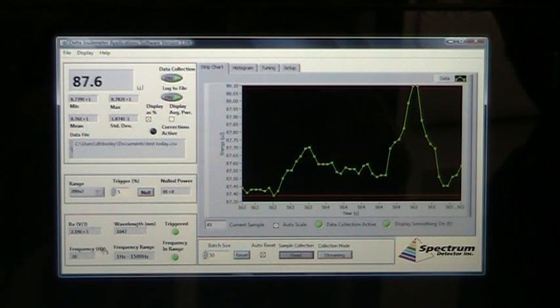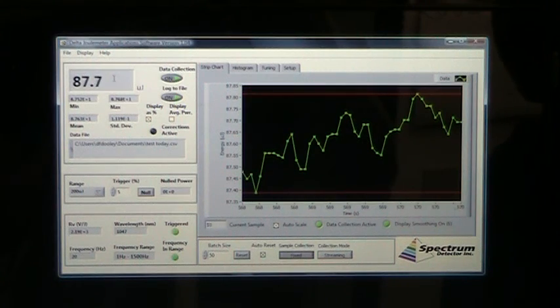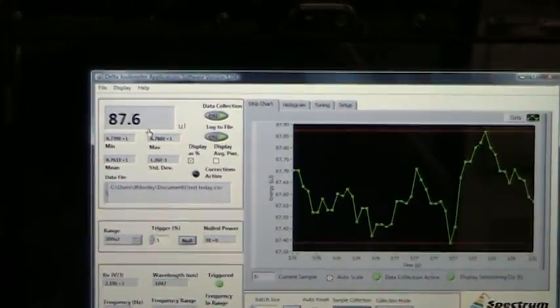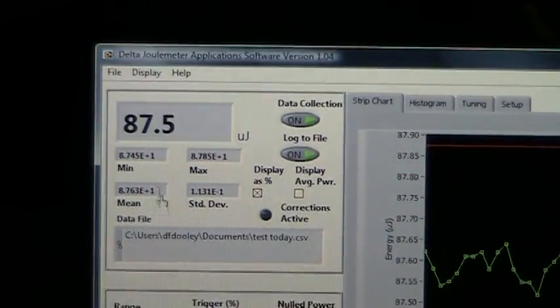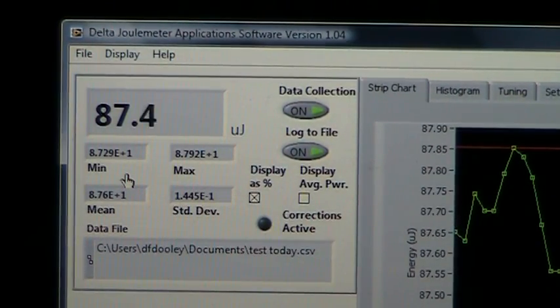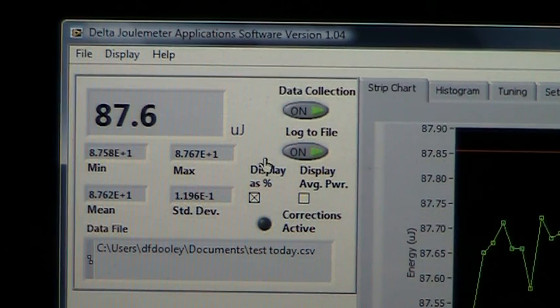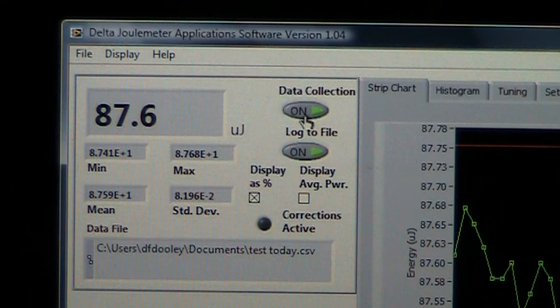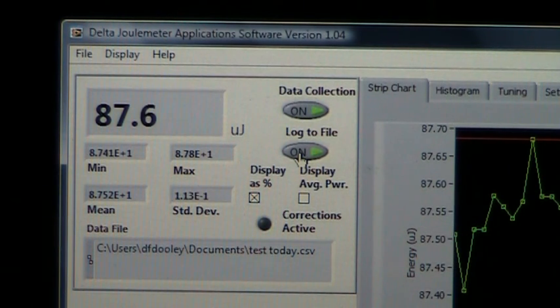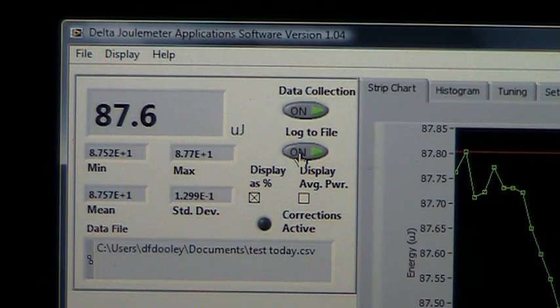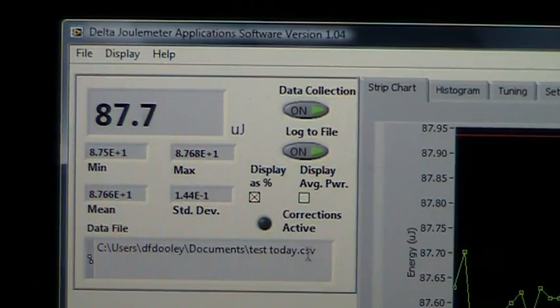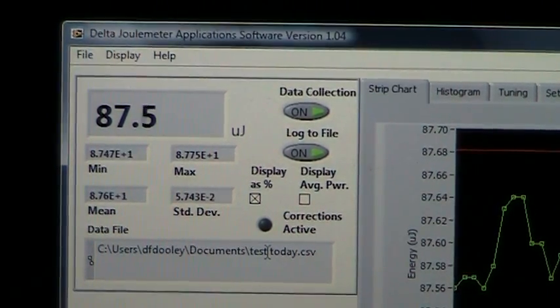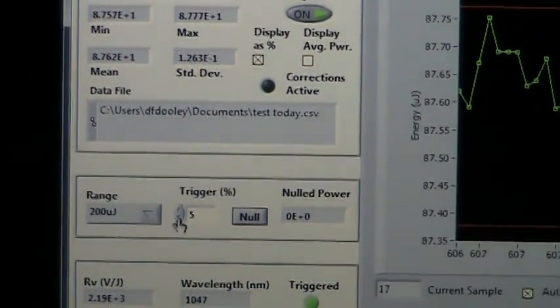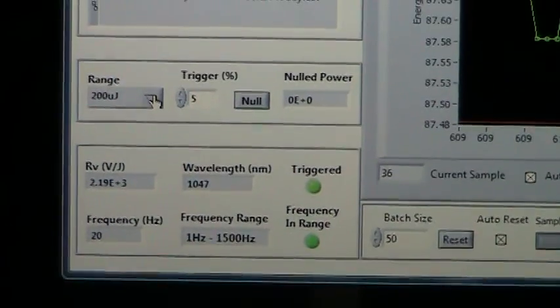This is revision level AM. This is the control panel, which is always visible to the user. In the upper left hand corner is a large window where we display pulse energy in real time. We're reading about 87 microjoules right now. Just below that are 4 windows where we display the calculated statistical data set: min, max, mean, standard deviation. Up in this right hand corner is the data collection button. This is how you turn data collection on and off. Just below it is a log to file button to log data to a file on your computer, and this window actually shows the file we have open to which we log the data. Now moving below this area we get to a couple of the controls. This is a range switch, basically.